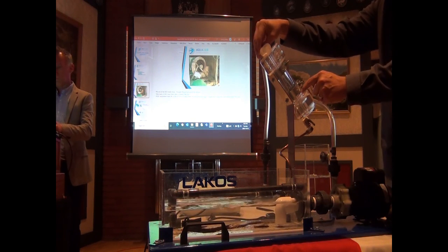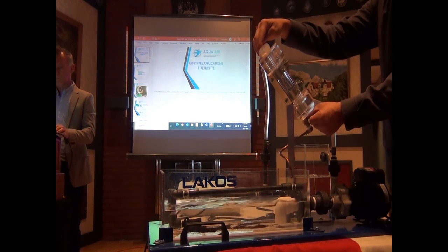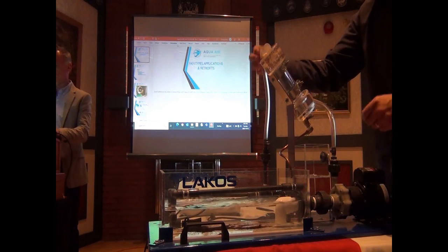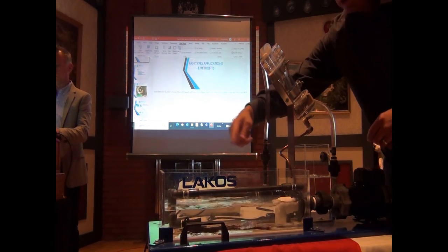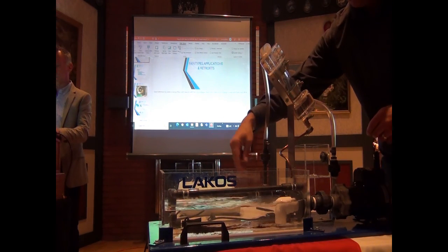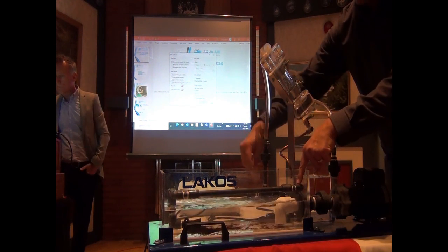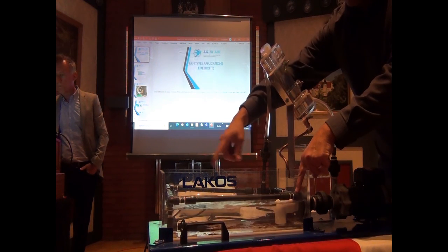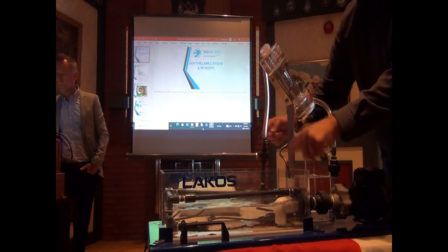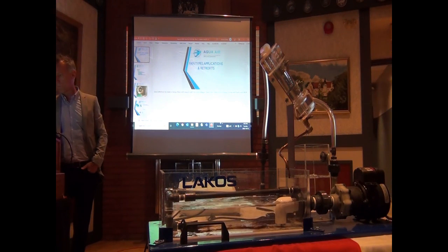That's actually pulling the clean fluid that's in the center up through the middle of this filter out to the system discharge. That clean fluid that's discharged gets sent out this line here, which represents your sweeper piping that's come back into your PVC piping inside your cooling tower, where that clean flow is pushed through a set of nozzles. And that set of nozzles, if they're properly adjusted, will push all of the dirt and debris towards your system drain, where it's picked up by your pump, pushed to the filter, and then filtered out. So why they call it sweeping? That's why they call it sweeping.